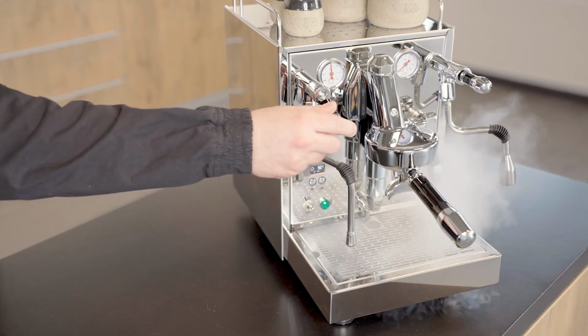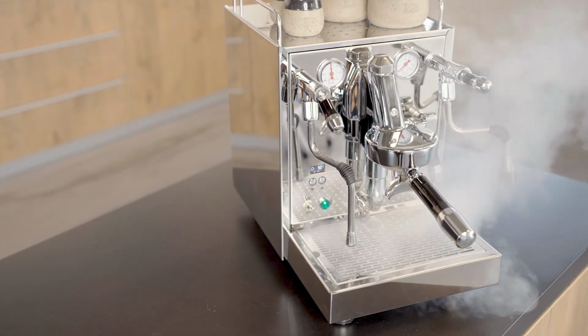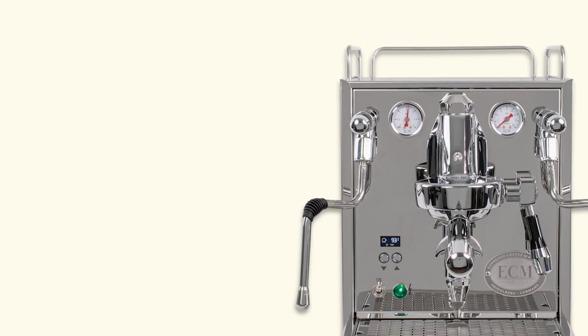Behind the low, medium and high setting for the steam, there is of course a certain temperature which is controlled by PID. Low means you're working with 124 degrees. Medium means you're working with 127 degrees, and high means you're working with 130 degrees steam temperature inside your boiler.